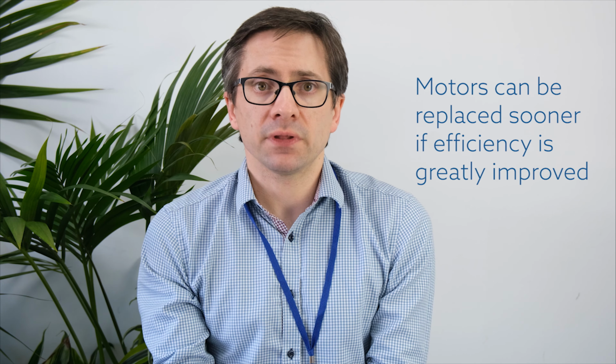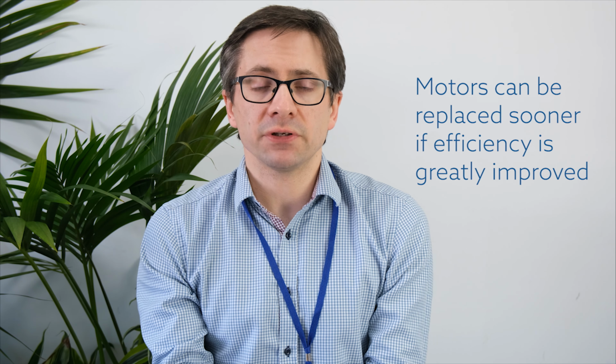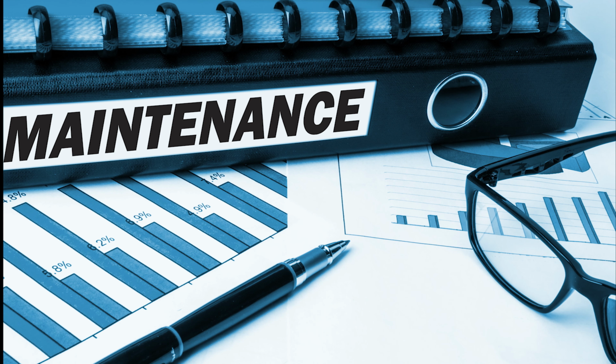Motors that are due for replacement within the next few years may be worth replacing sooner if there is the potential to improve their efficiency at the same time. Motors should be reviewed well in advance of their anticipated end of service to work out if or when an efficiency upgrade would be worth doing in terms of the capital cost versus the kilowatt hours it might save. For this reason, a site with a large number of motors should keep a register of them and track both their maintenance records as well as their predicted and measured energy consumption.